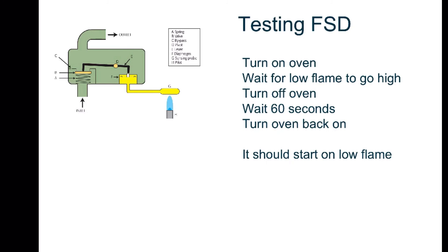If the FSD is working correctly, then when you restart the oven it's restarting from cold and it will only give you the low rate, because that's the only bit that the gas can get through. If the oven starts up on high flame, then the FSD is broken and the appliance is immediately dangerous.